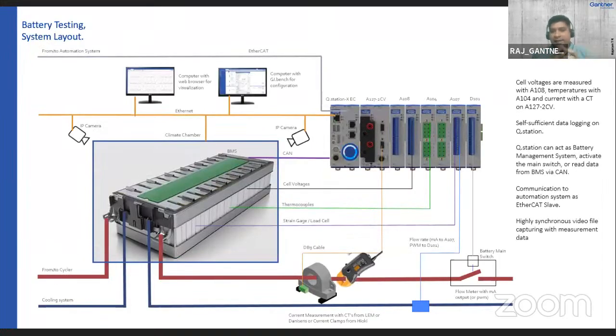This slide shows the complete system layout for a battery testing application. The complete battery is under test, we're measuring cell voltage, temperature through thermocouples, and structural stability through strain gauges or load cells. We also capture real-time position of the battery through video. We can communicate with battery management systems through CAN bus or Modbus, and our controllers can even act as a battery management system.